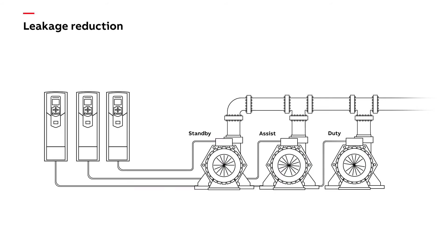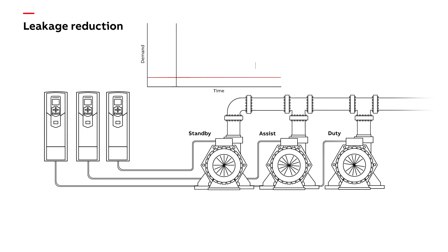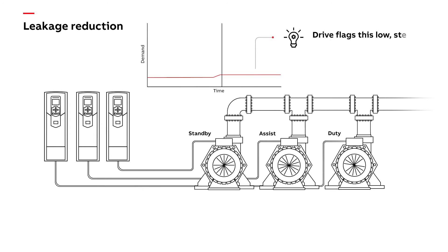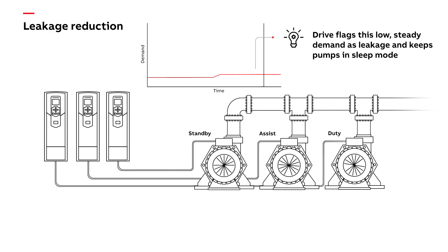This could reduce leakage by up to 80% in the night. Some drives also have a sleep function which will enable the pump to rest in the case of very low demand. If the drive detects a low demand which remains steady, this is detected as leakage and allows the pump to remain in sleep for a little longer.